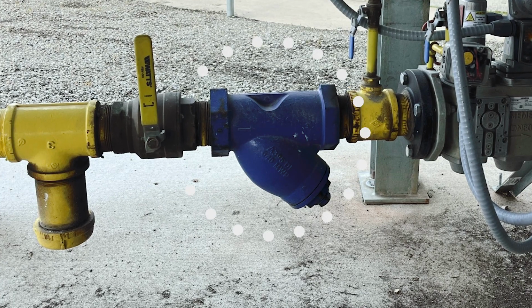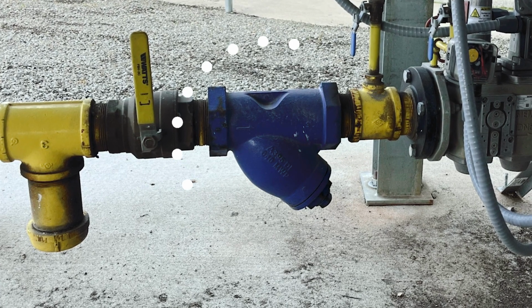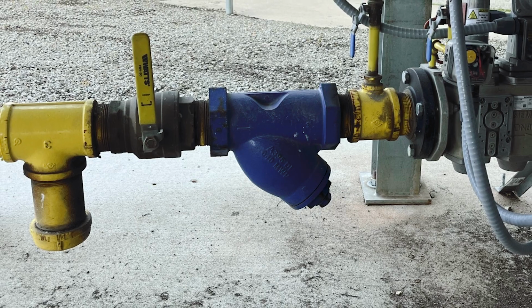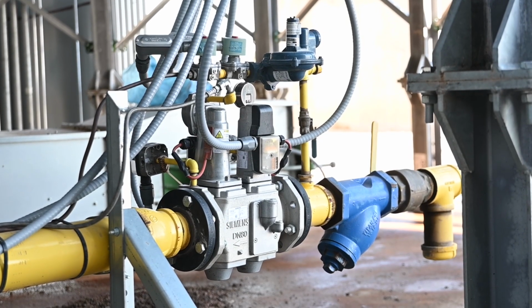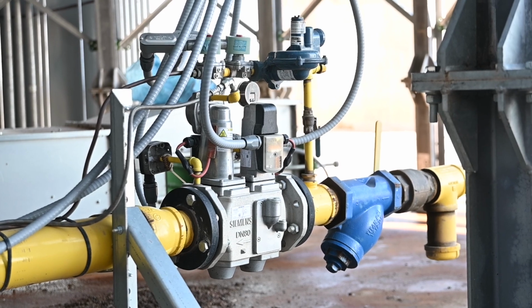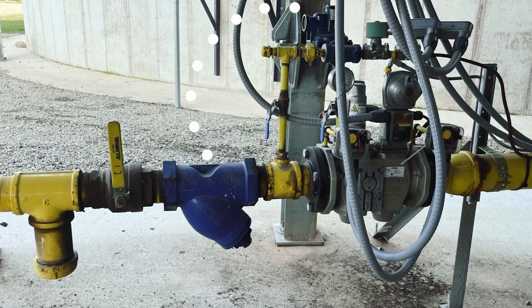The next thing is called a Y strainer. It's the blue component here. The bottom part of the Y strainer can come out, and there's a screen inside there that should be checked and cleaned once a year. Anything that could accumulate, such as metal filings or shavings, could collect in that screen, and that should be checked yearly as well.